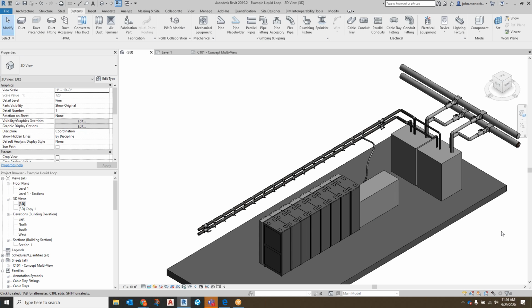I'll take an example. You might have a liquid cooling solution that does 100 kW. This is a rear door heat exchanger on a rack, which does 35 kW. If I assume I've got 8 racks at 35 kW and do the math out, I could say there's a pretty good size for an example. But if you're this guy, you say 100's actually what we want to base it on, or 200. And then the CDU manufacturers are going to have a different number.